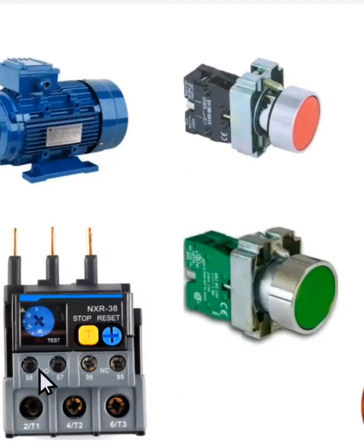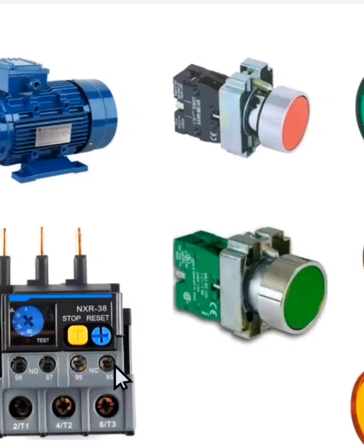You usually wire the trip light through it, because once this overload trips, this side becomes continuous. So we connect our lights through it to enable us know when this has tripped, and the control is connected through this contact, so that whenever this trips, this becomes normally open, de-energizing the control. By so doing, the contactor is off and the motor is protected.